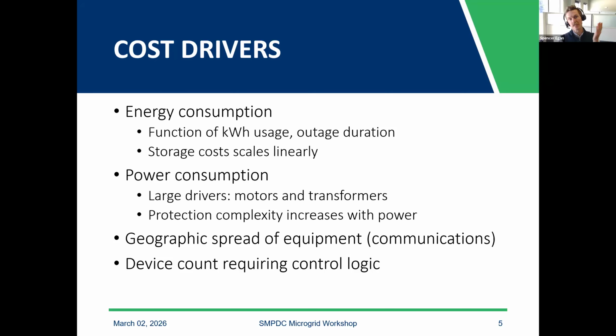Power is the instantaneous usage, a function of kilowatts, which might reflect your demand charge. But when designing a microgrid, you don't care just about the 15-minute demand that utilities bill for — you need to concern yourself with smaller time scales too: your 1-minute, 1-second, or even sub-second power usage during events like connecting a transformer or starting up a motor.